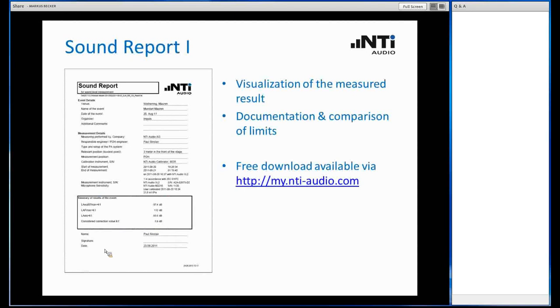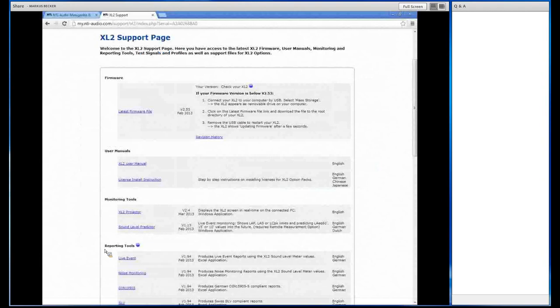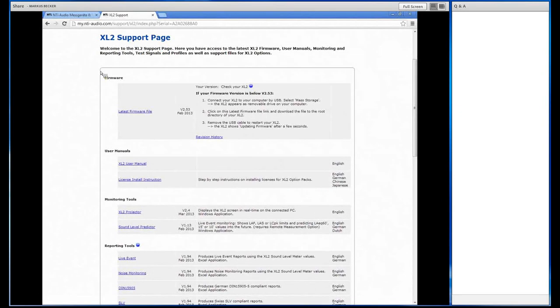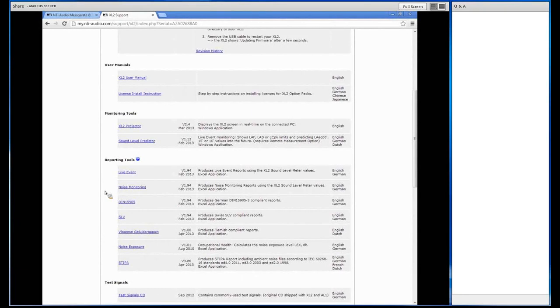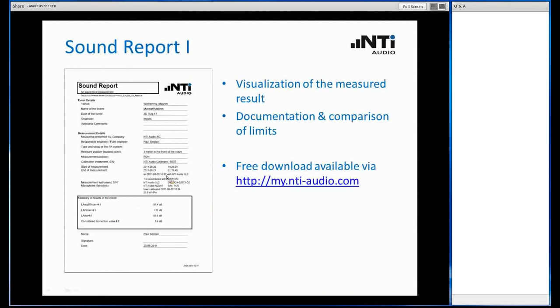Some words about the reporting. NTI offers a template for this sound report. I just show you how you can get it. Here we have the my NTI audio website. By registering at NTI audio you get access to this website, and here in the XL2 support page you see we have the reporting tools. By clicking on these links you will receive the corresponding Microsoft Excel sheet, which is already prepared to create exactly this kind of report. Creating means it acquires the logged data from the XL2, includes it into the report the key measures, what was the maximum level and so on. You can add your own name or the name of the event and print it out as a reference.